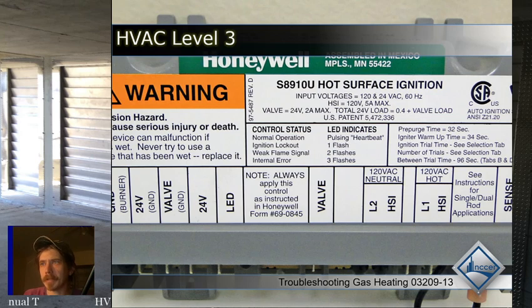The compressor contactor will come on. If you jump R to G, the indoor fan will come on. If you jump R to W, the electric heat or the furnace will come on, and so on and so forth. So just remember that that's a good method of testing it, and those are the things that are energized. But remember what your terminals are that we just talked about, and remember that you can jump them over to energize those things at the thermostat sub base.